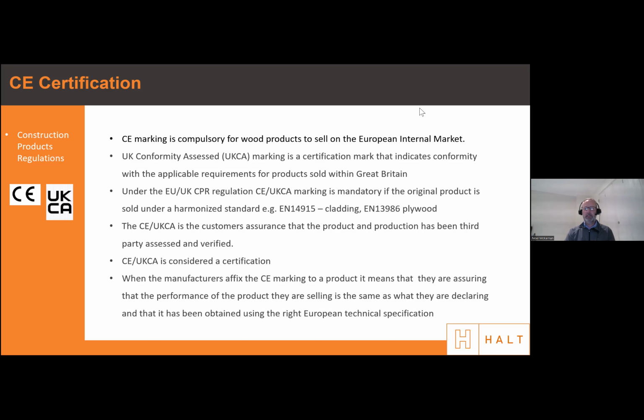So CE certification is critical to the whole impregnation process. A notified body needs to be involved in regular auditing of that manufacturing process. They need to go through in great detail each production report that's produced to ensure the material being produced is to the correct standard. It all goes back to the field of application and the testing process that was carried out. If a material is declared on the test report to have 48 kilos of fire retardant per cubic meter, the manufacturing process must ensure it's getting at least 48 kilos of fire retardant per cubic meter into that product. This is where CE certification comes in.